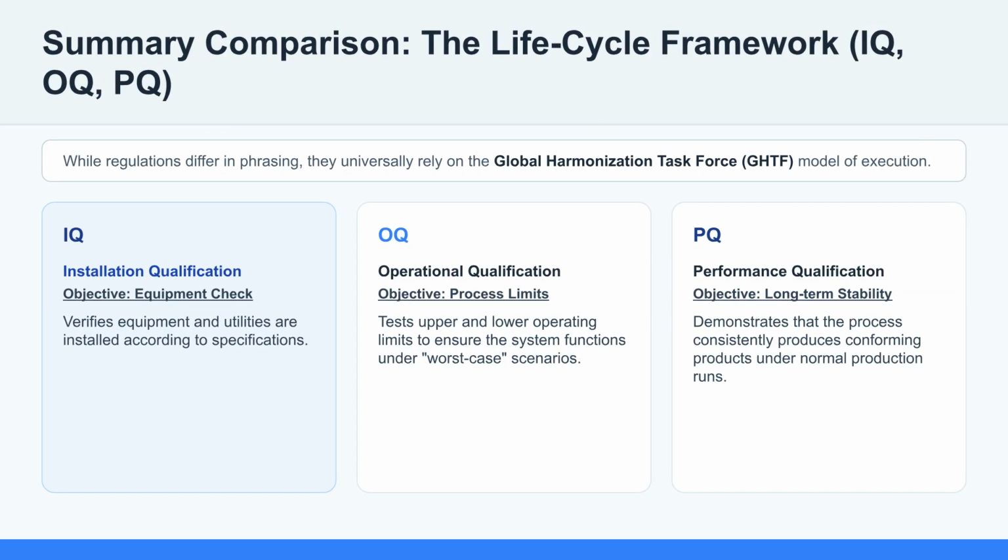Regulations rely on the GHTF's lifecycle framework of installation, operational, and performance qualifications. IQ verifies equipment installation. OQ tests process limits under worst-case conditions, and PQ demonstrates long-term stability and consistent product conformance.